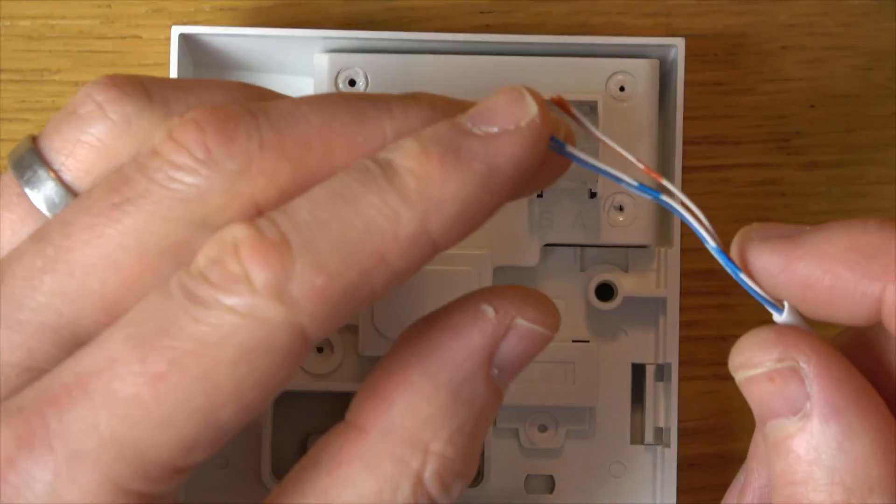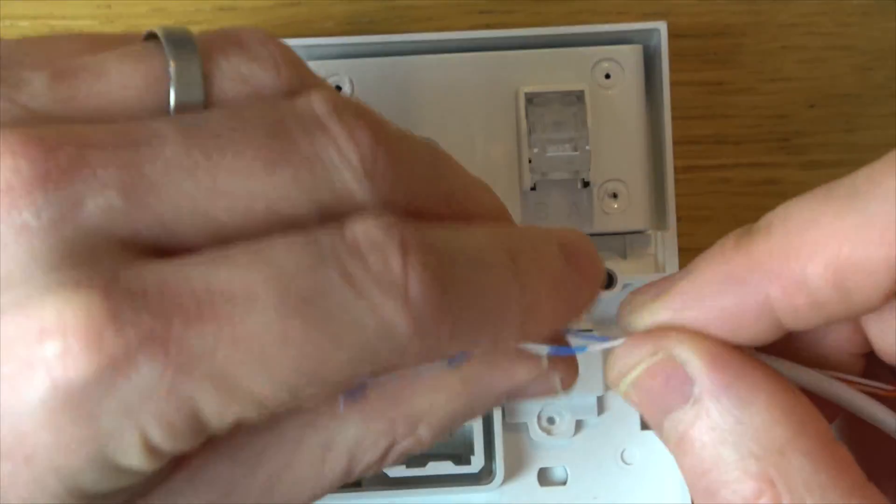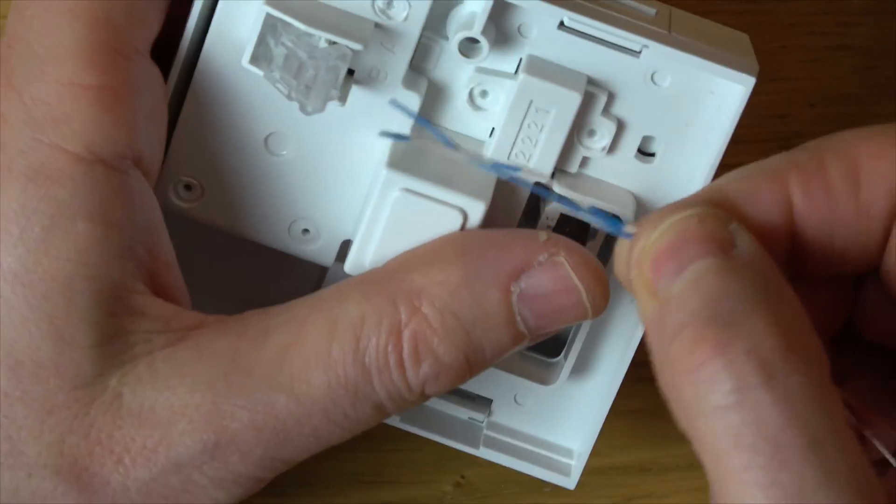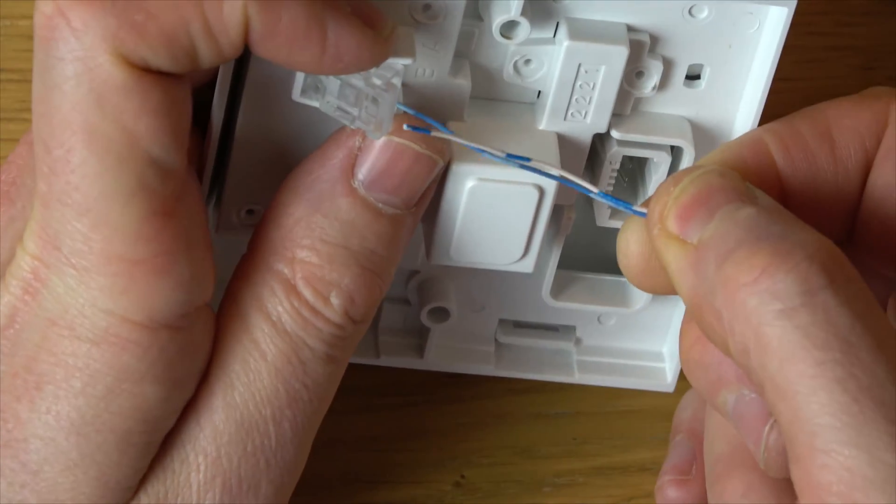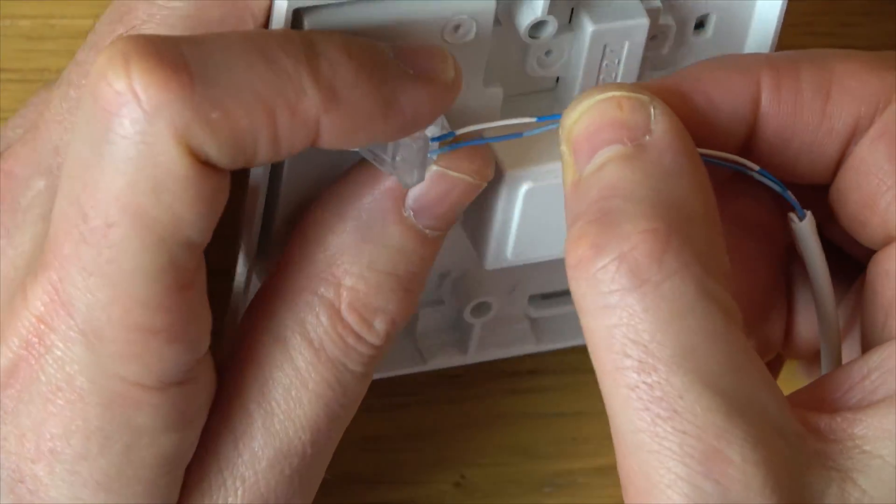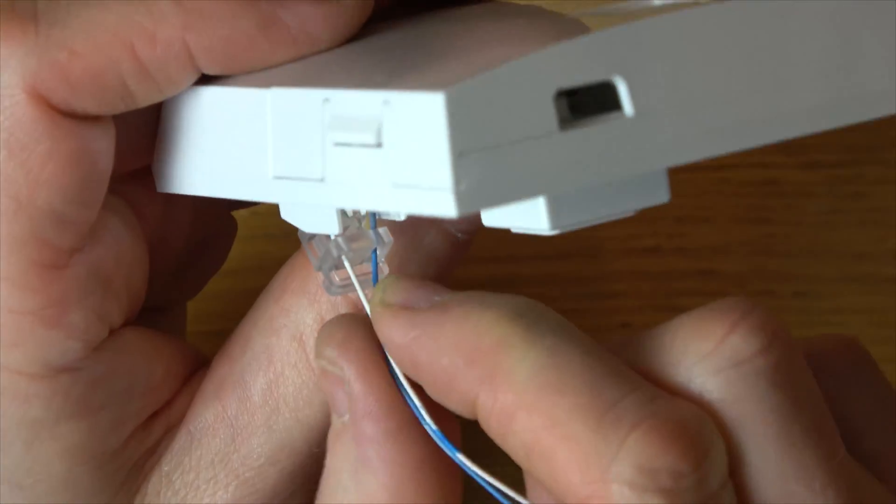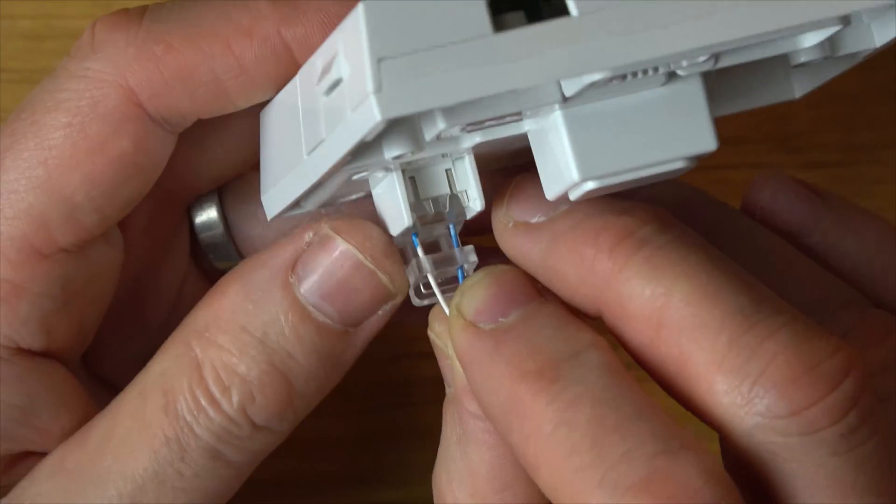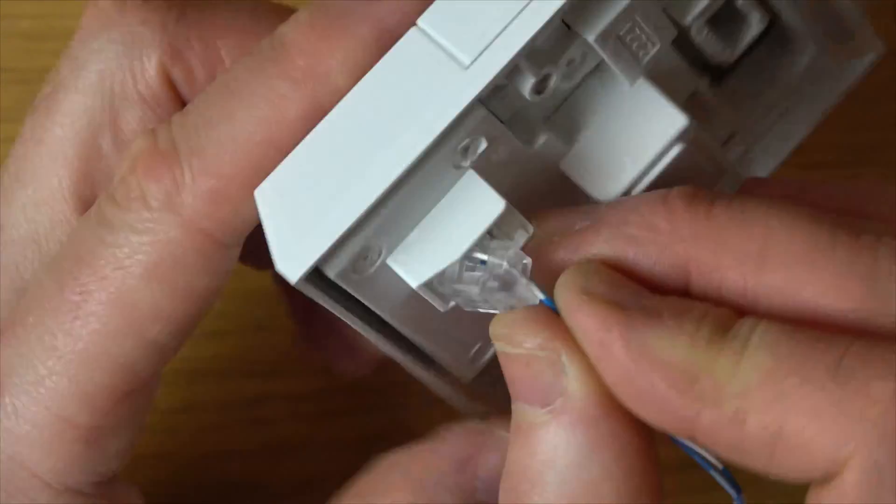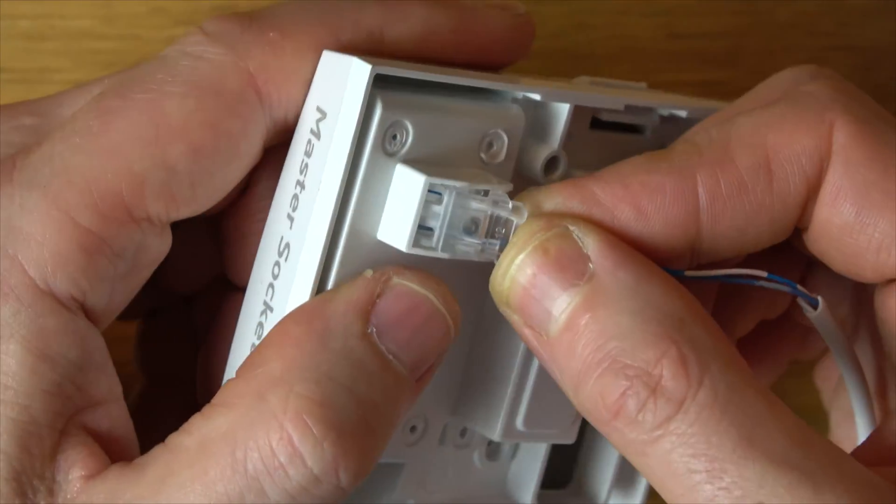Now we're going to be connecting up the blue and the white blue, but you might have green and black, you might have orange and white, it will just depend on the age. So we're going to be putting the white blue into A and the blue into B. Basically we have these little holes here and then more holes at the back. You need to make sure that the wire goes through both lots of holes. You can see a visual indication on the top that it's gone right to the very end.